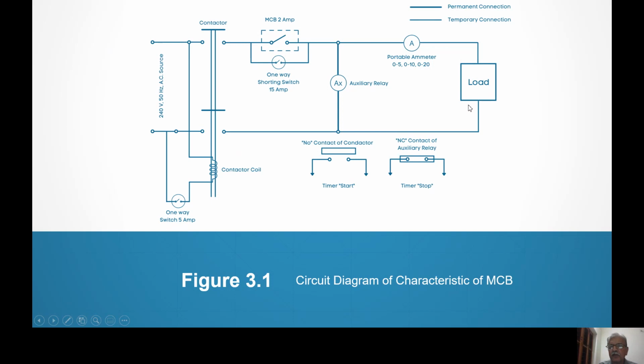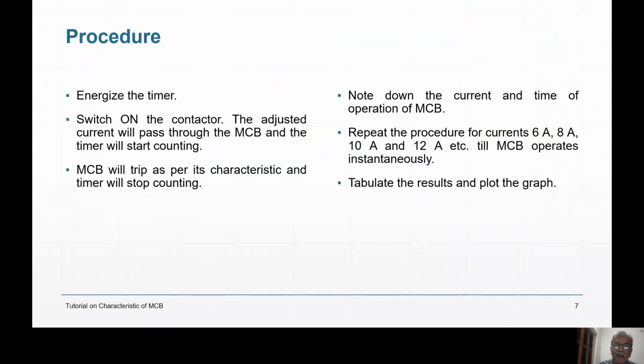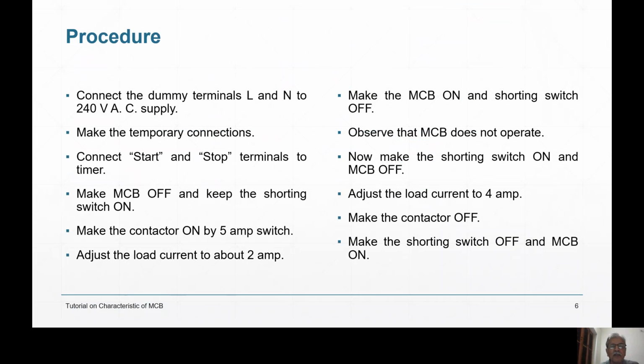Then there is a load, a lamp load, right? And the NC contact of the auxiliary relay. Why the NC contact? Because when the MCB trips, the auxiliary relay de-energizes and its NC contact will stop the timer. So you will know the time of operation of the MCB. So pass the current, note down the current, note down the time, take different readings and plot the characteristic. Actually, this much is the experiment. There is nothing more in the experiment.